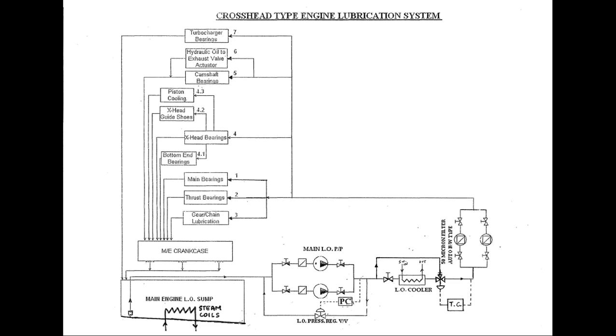The discharge of the pump is provided with a pressure regulating valve which automatically controls the discharge pressure of the pump irrespective of lube oil temperature. Low lube oil temperature leads to more viscous oil, increasing resistance and thereby increasing the pump discharge pressure. The pressure regulating valve regulates this discharge pressure automatically.